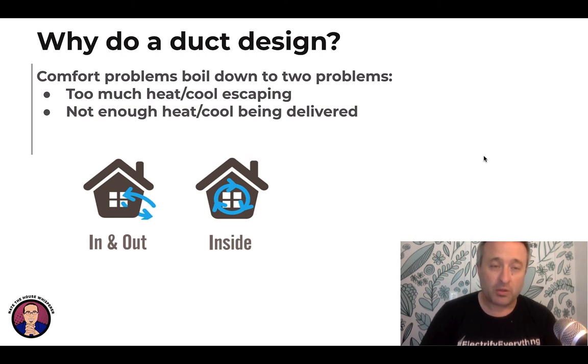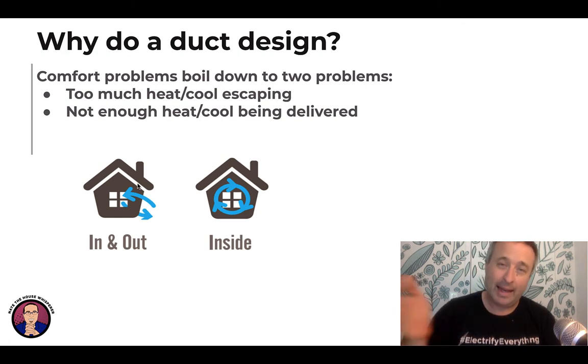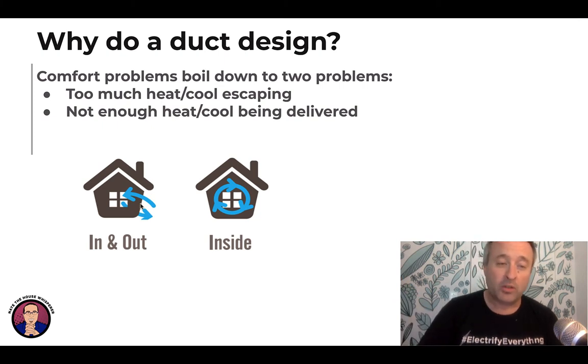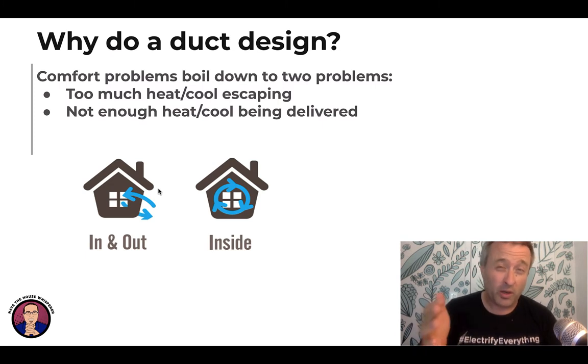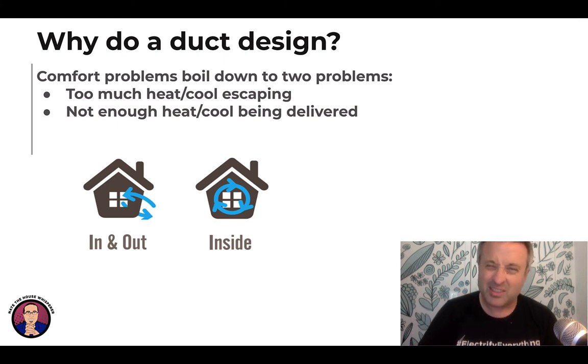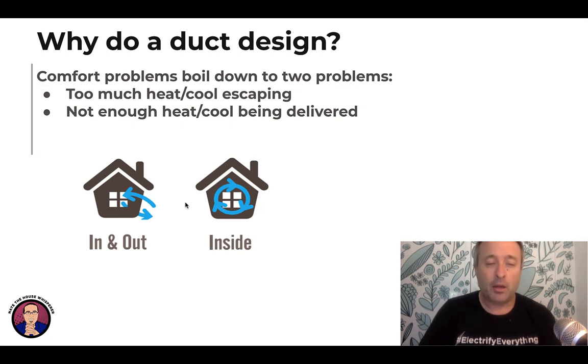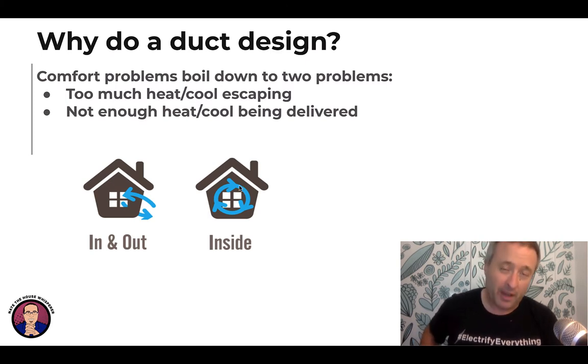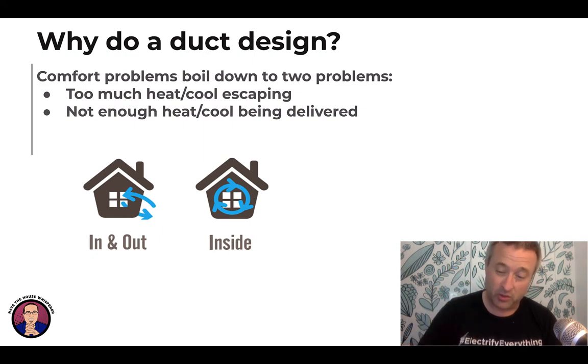Here's what it looks like: you have to deal with heat, air, and moisture flowing in and out. Air is by far the most important of those because heat and moisture travel on it. Once you have a house reasonably tight — doesn't have to be perfect — what we find is a one-to-one ratio of blower door leakage to square footage is about where things start getting decent. Sometimes you need to be in the 0.7 range, but somewhere in that range is good enough to control problems with HVAC. Then you need to make sure that the HVAC is adequate.